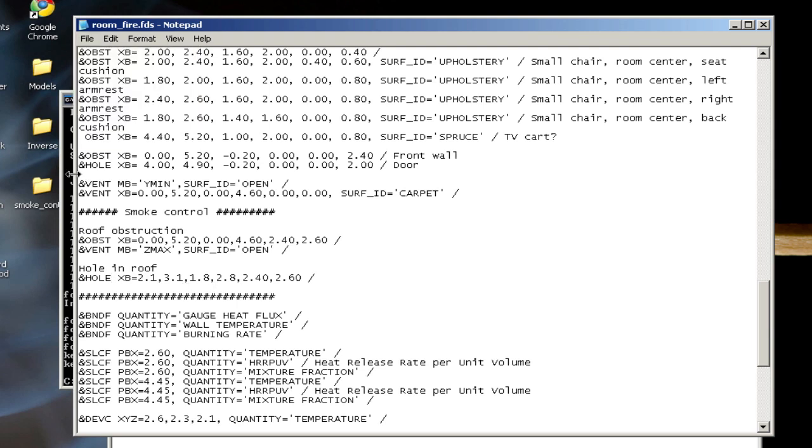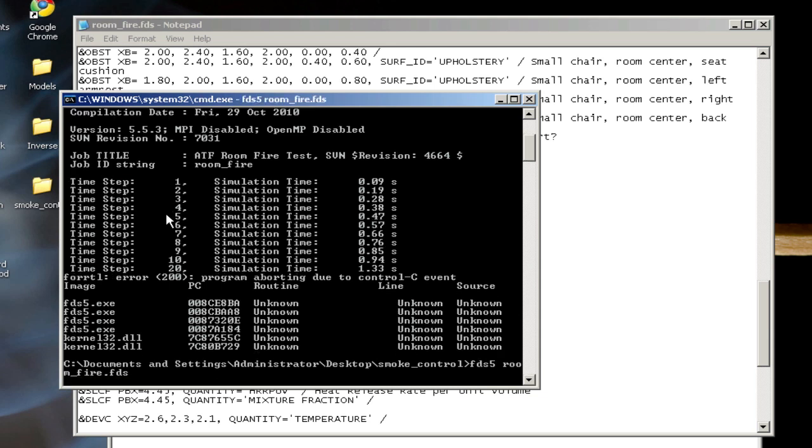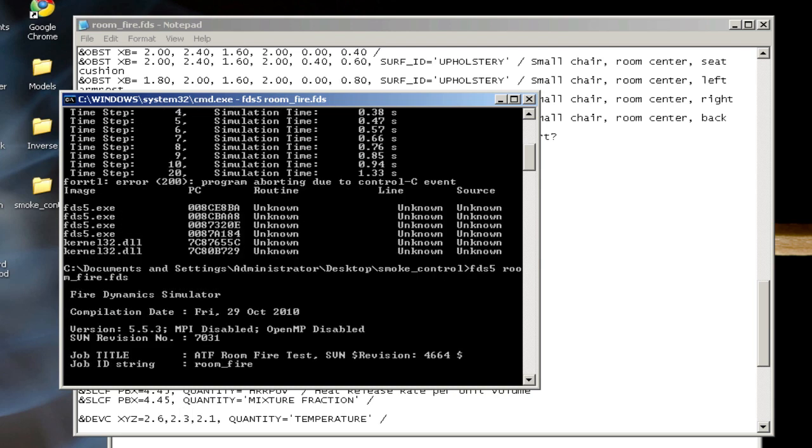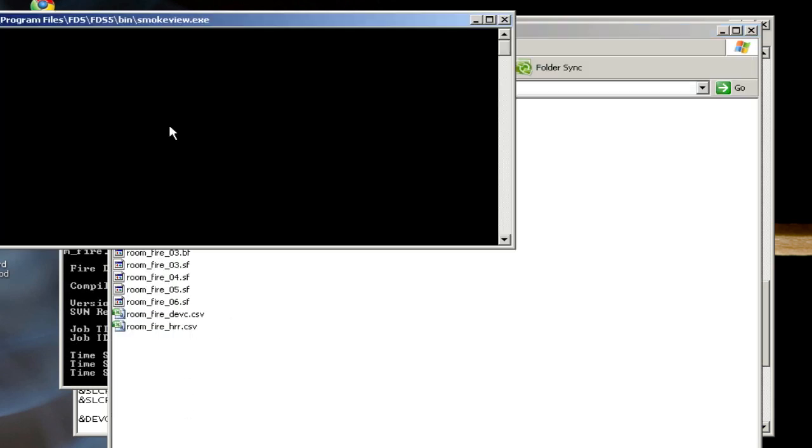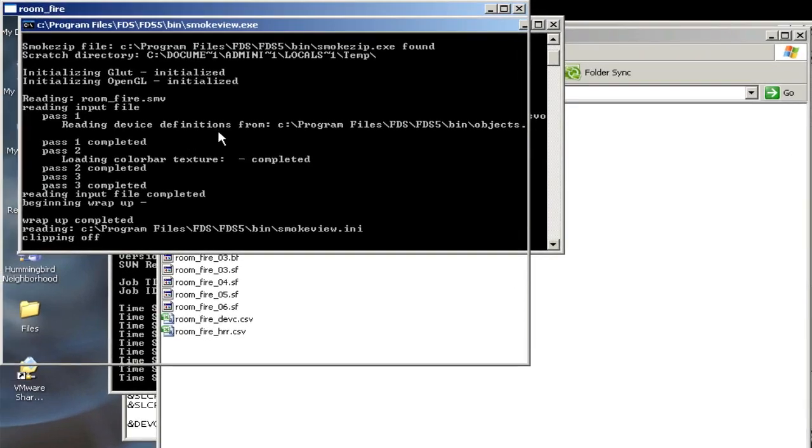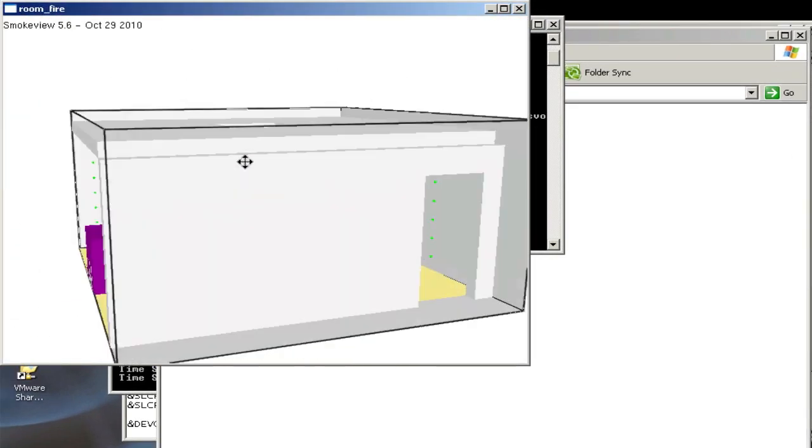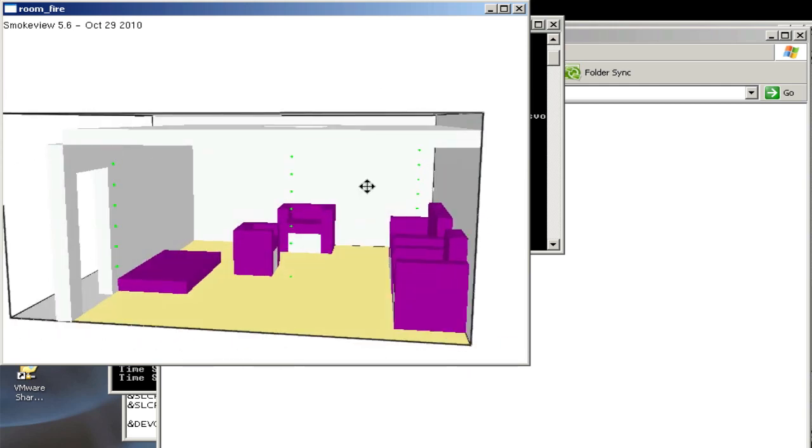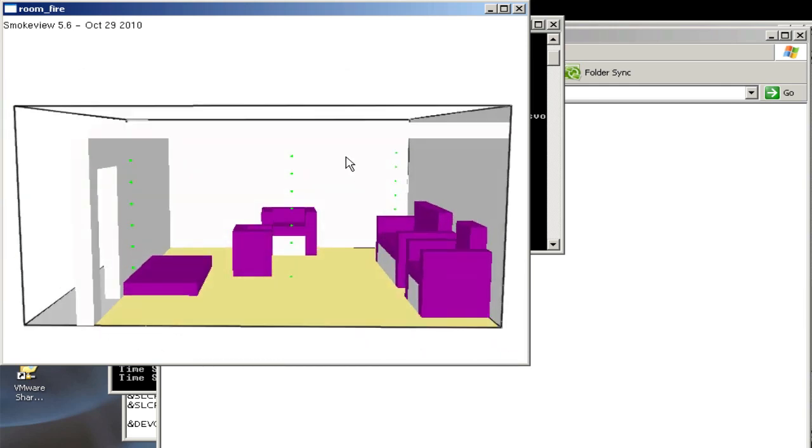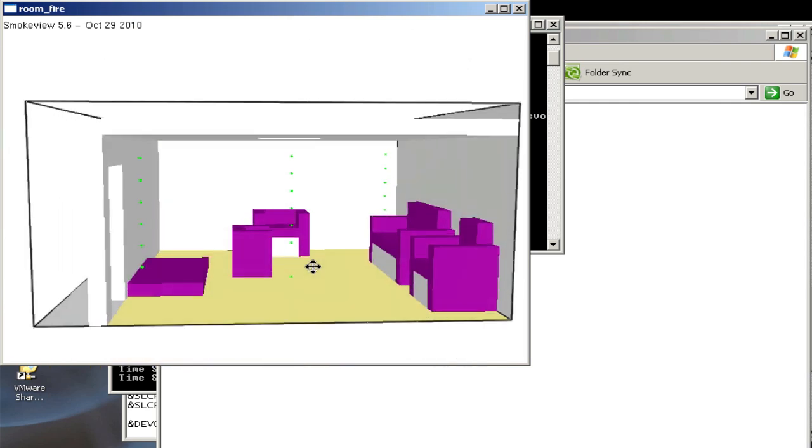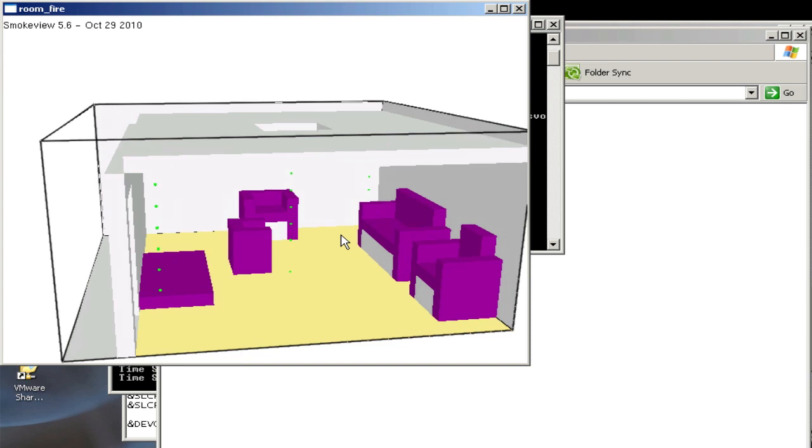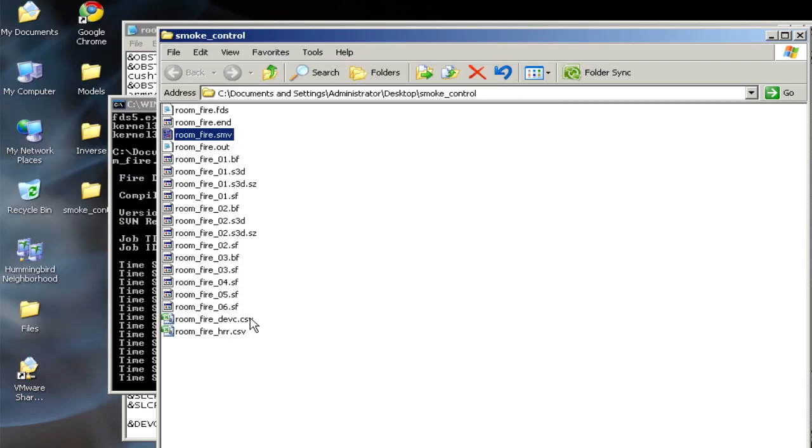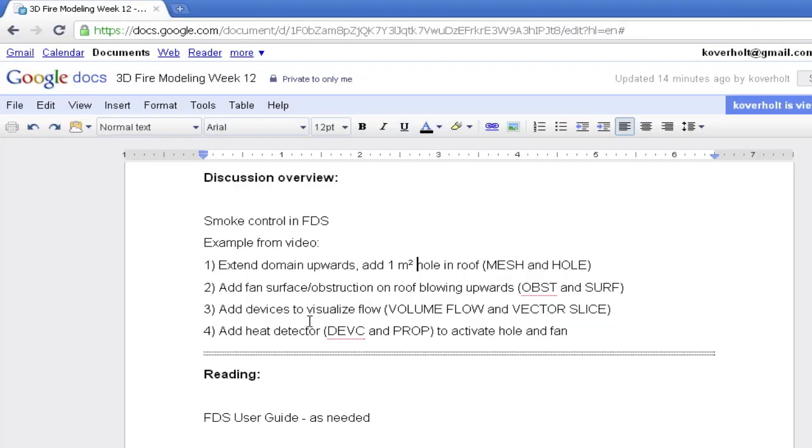Click save, and I should be able to rerun this case by rerunning FDS5 roomfire.fds on the new input file. And after that starts running, in a second I can open the smoke view file, and we should be able to see the changes that were made to the model. So now here's our roomfire case, and we now have an obstruction representing the roof, and we see that we've extended the domain a little bit above there, and we've also created a hole through that obstruction, which is active from the start of the simulation. So if I were to turn this on, I'd be able to see natural ventilation and smoke flowing through that vent. So if you're doing natural ventilation, you're actually done at this point. You can set your hole to be created via time or by some device. But we have a few more steps we want to do for mechanical ventilation.